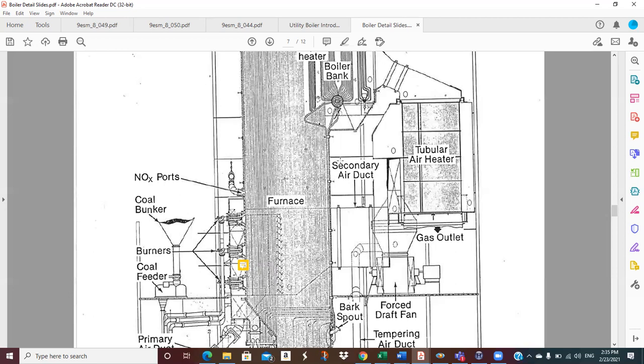Drag your combustion out so that you don't just hit it one time with a real high temperature. If you can minimize that maximum temperature, you can minimize the NOx production. Because one of the main mechanisms by which these boilers produce NOx is by dissociation. So at higher temperatures, N2 will split apart into two nitrogen atoms. And oxygen will split apart, or the oxygen doesn't even have to split apart. If the nitrogen splits apart and it can grab onto an O or an O2, guess what? That's NOx.